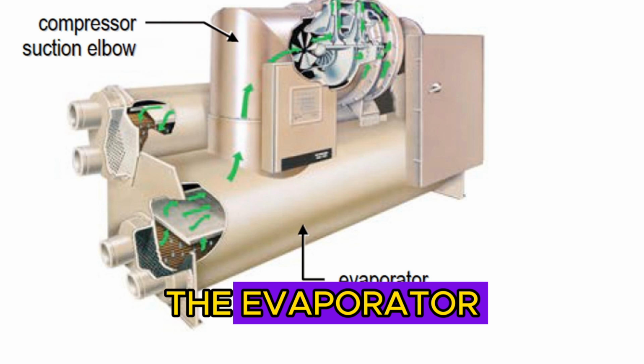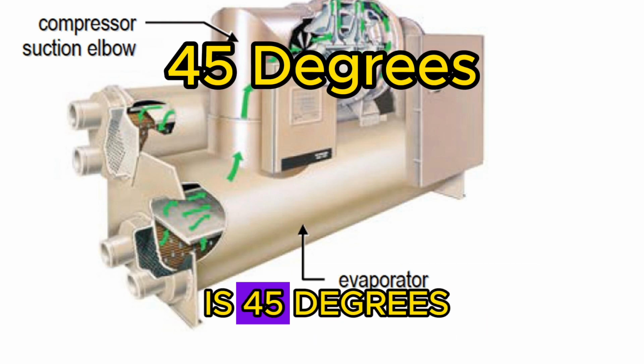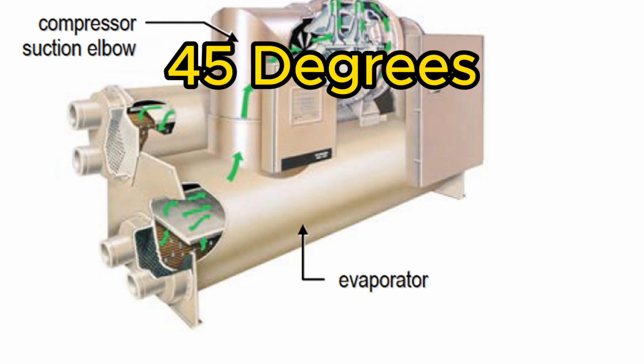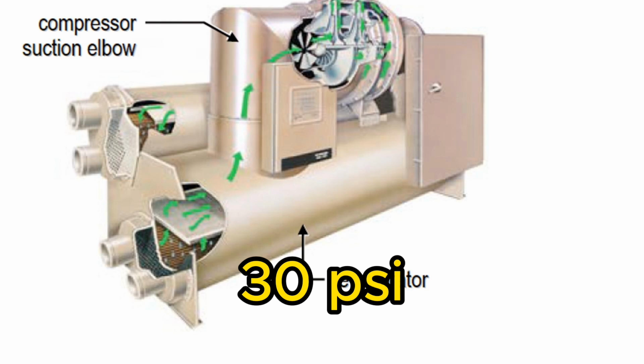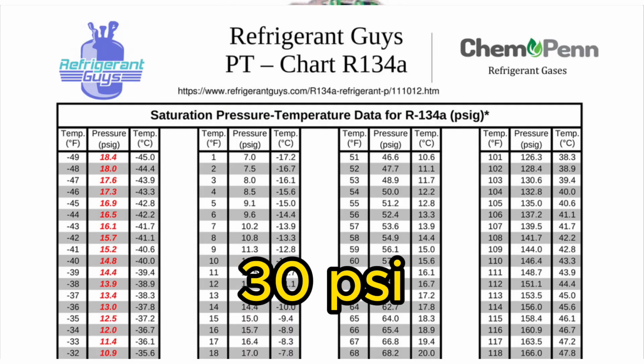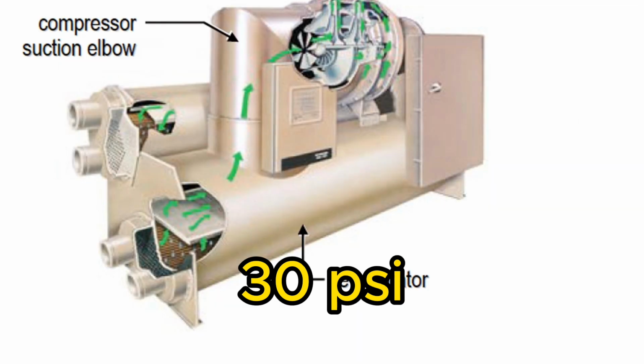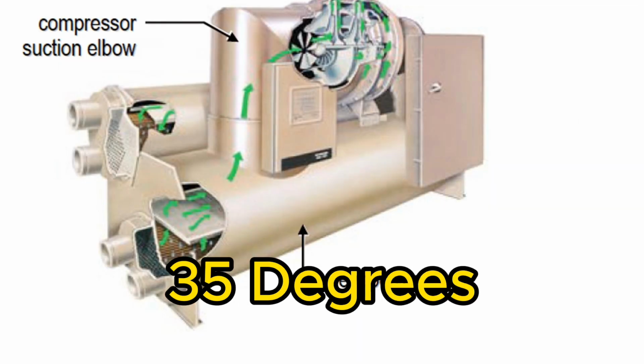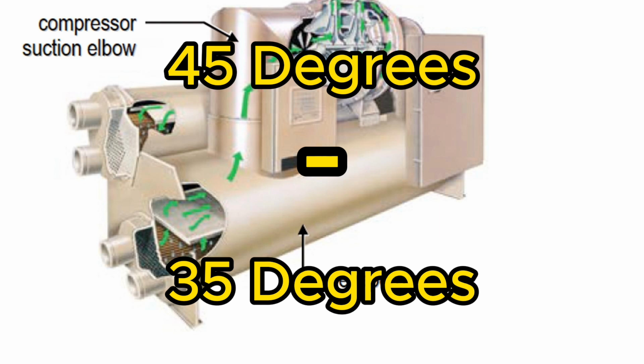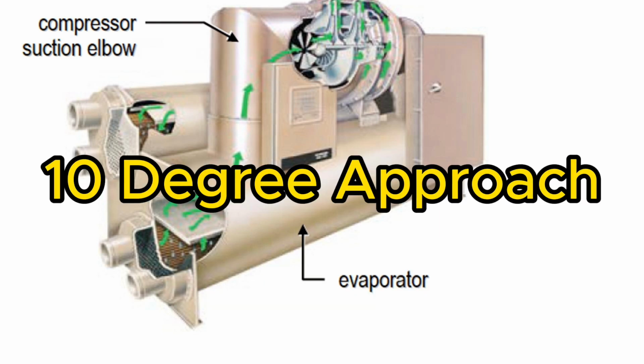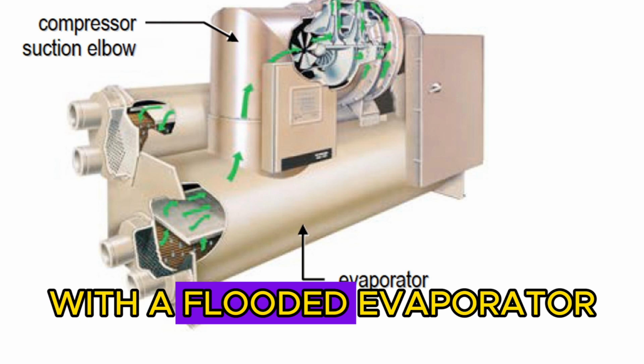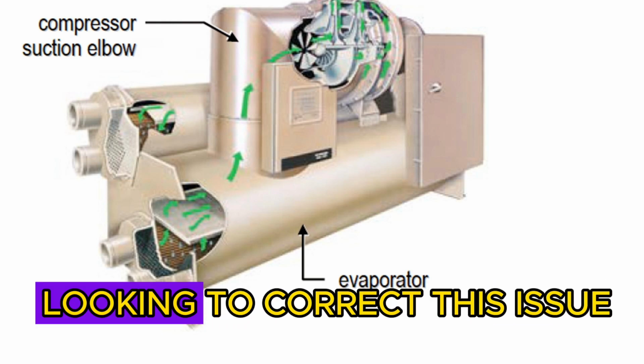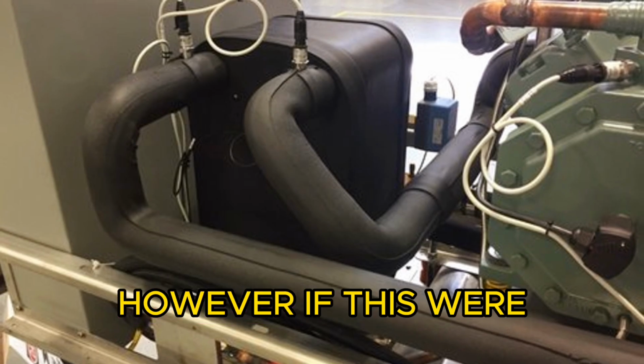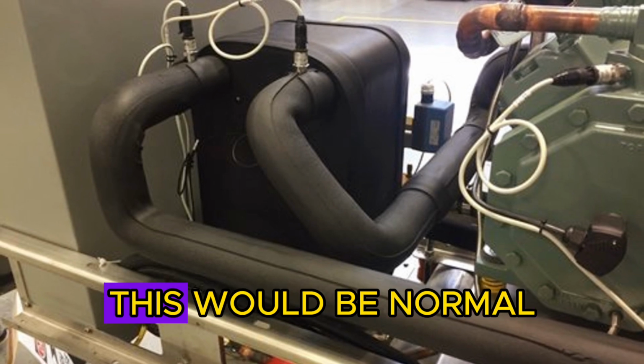Imagine a chiller with 134A in it. The evaporator leaving chilled water temperature is 45 degrees, and the suction pressure is 30 psi. Convert the 30 psi to its saturation temp on the PT chart, then deduct that from the leaving chilled water temp. 30 psi saturated is 35 degrees. Take 45 minus 35 and you get an approach of 10 degrees. If this were a centrifugal chiller with a flooded evaporator, I would immediately be looking to correct this issue. However, if this were a brazed plate style, this would be normal.